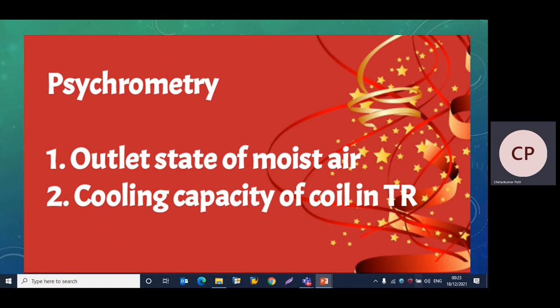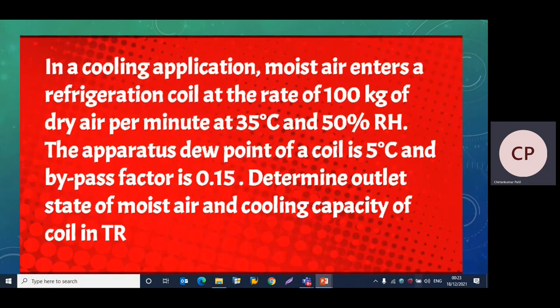Hello friends, this is Priyanka. Today we are going to solve a problem on cooling and dehumidification with the help of a psychrometric chart. In this problem we are going to find out the outlet state of moist air and the cooling capacity of the coil in tons of refrigeration. Moist air enters a refrigeration coil at the rate of 100 kg of dry air per minute at 35°C and 50% relative humidity.